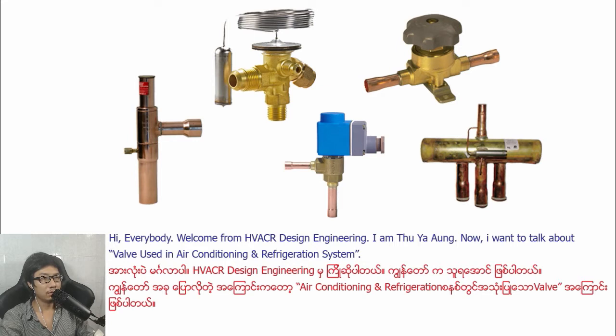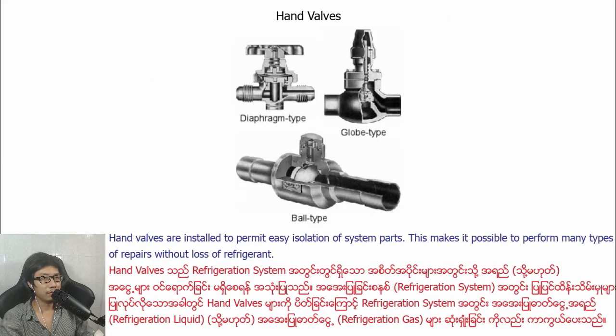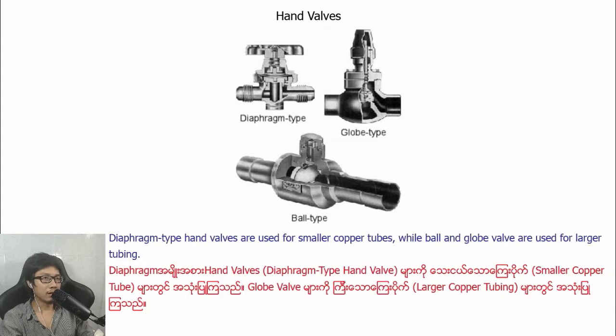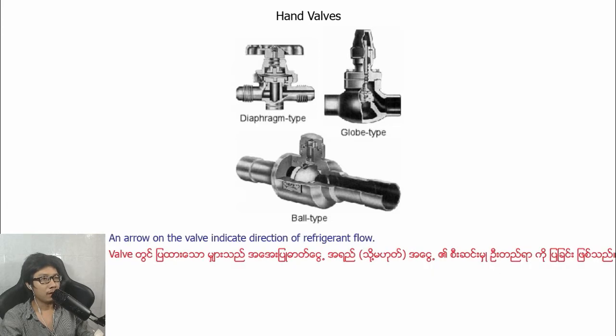Now I want to talk about valves used in air conditioning and refrigeration systems. Hand valves are installed to permit easy isolation of the system, which makes it possible to perform many types of repair without loss of refrigerant. Diaphragm type hand valves are used for smaller copper tube, while ball and globe valves are used for larger tubing. An arrow on the valve indicates the direction of refrigerant flow.